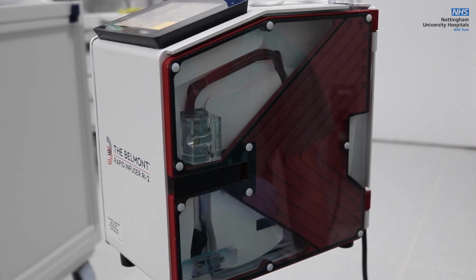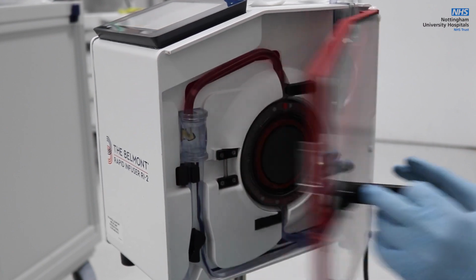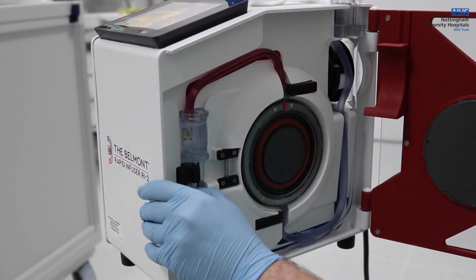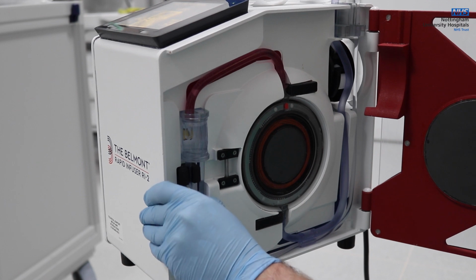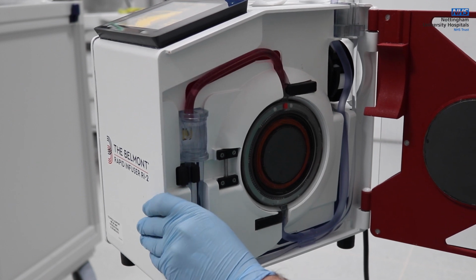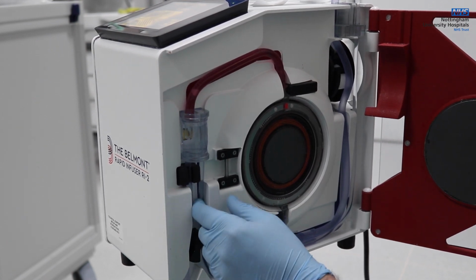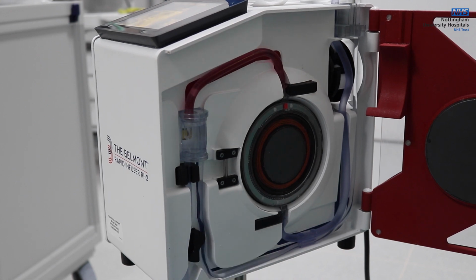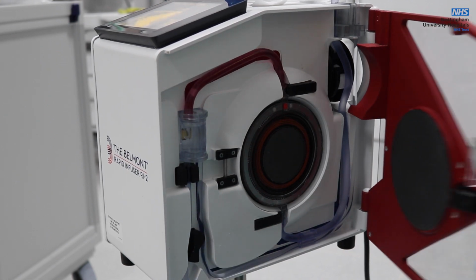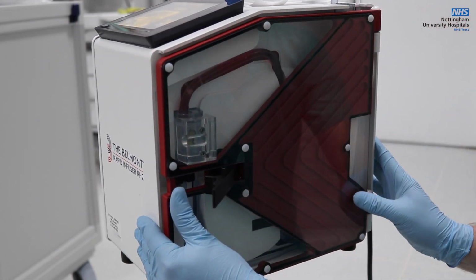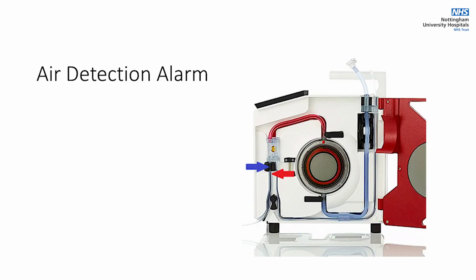Air detection alarm. Open the door, squeeze tubing directly below the air detector sensor to clear the air. Recirculate to remove air in the line. Reseat the tubing in the air detector sensor. Replace the disposable set if there's a leak. If the door is open, close the door to silence the alarm and resume. If the error persists, clean the sensor as indicated by the blue arrow with a cotton bud and dry.